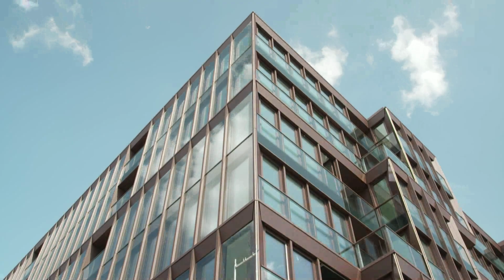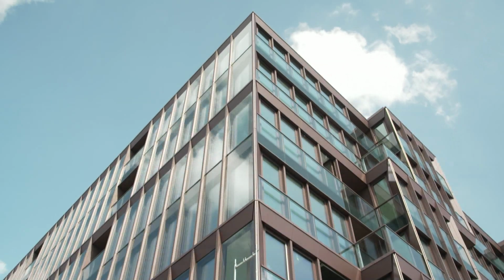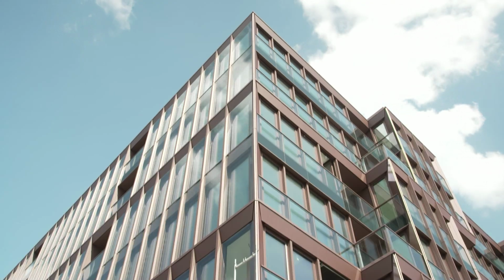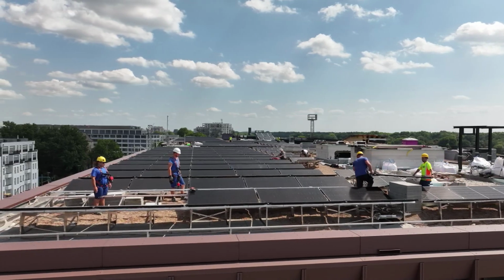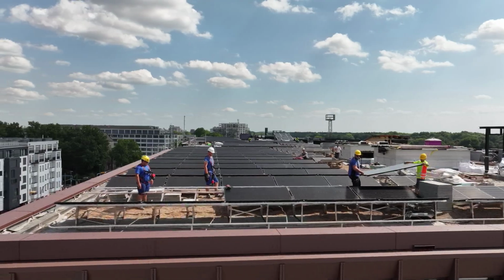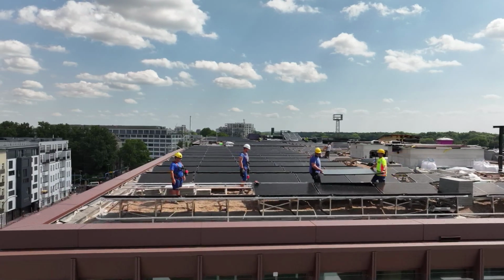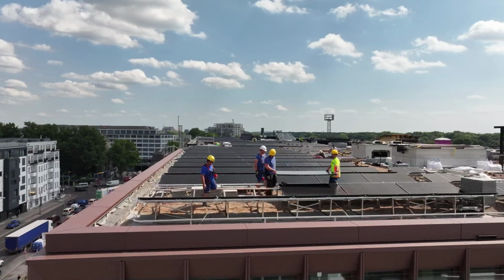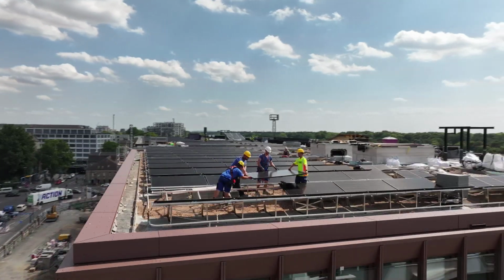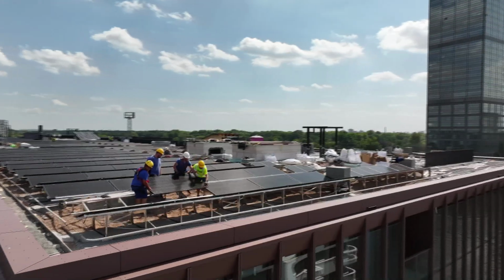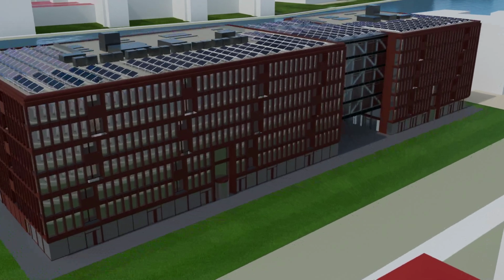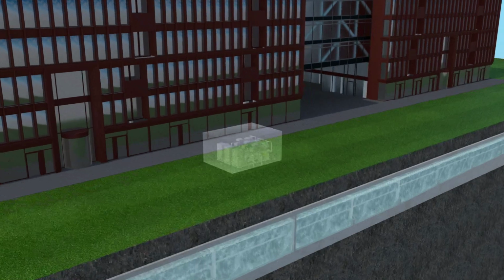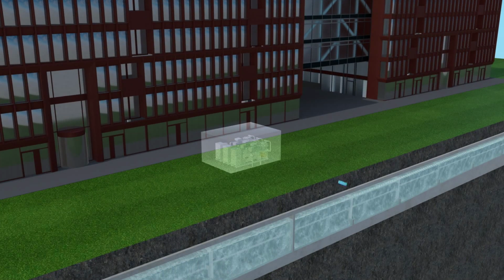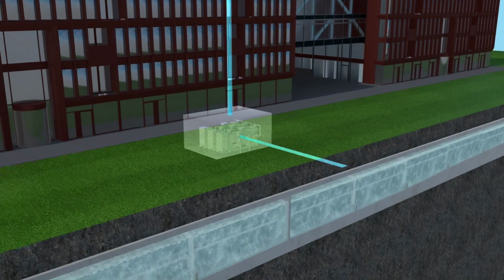Conventional air conditioning systems generate a hot stream of air that is blown out of the appliances and heats up the surroundings. With PVT modules, the heat escapes as infrared radiation directly into the night sky. In the dockyard, however, cooling via the bored piles and the ground is not enough at the height of summer due to the large glass facade. In very hot weather, cooling therefore comes from the ice storage tank. The cold water initially flows directly back to the radiant ceiling panels. The ice block then begins to thaw.